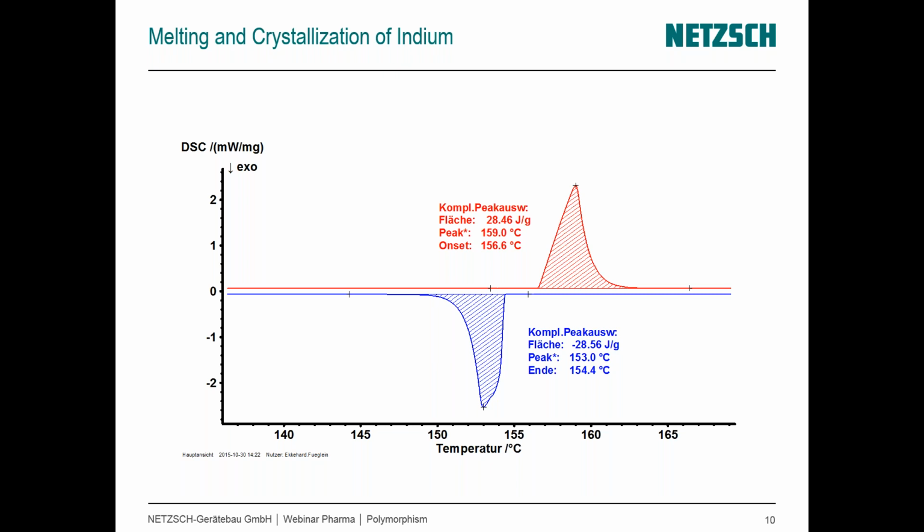I know that here in the US, where I'm broadcasting from, many providers of thermal analytical instrumentation have the opposite convention. All software packages can allow you to reverse this. So really we get the exact same information. It's just a question of, is endo up or endo down? So we also have this nicely color coordinated, red and blue, red intuitively for heating, blue more intuitively for cooling. And so what we have here is indium. This is one of the most commonly known calibration standards used for looking at DSC. Now, what makes it a calibration standard?